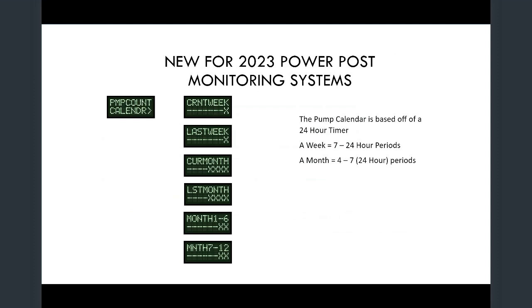So that could let you dial in. Well, why did I have extra pump cycles that day? And you're asking, how do we show you 48 when you have 1 digit? Well, if it flashes a number, then it's showing you more than the single digit. So it'll just stay solid, like a solid 7, or it'll be 2, 4, and it's like a 2-second flash. So 2, 4 would be 24 cycles.